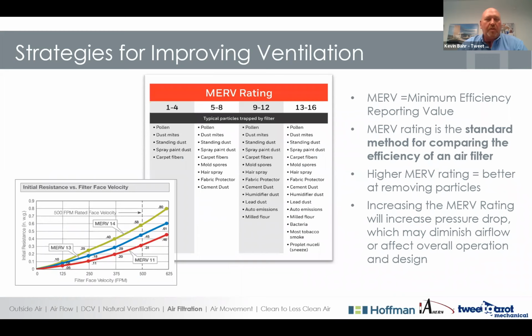Another strategy for improving your ventilation is through air filtration. I'm assuming you all have air filters in your systems, and traditionally they're a lower MERV rating, possibly an 8. MERV stands for minimum efficiency reporting value. It's how their particulate capture capability is measured. As you increase to a higher MERV filter, which seems like an easy resolution, you take your filters out and you put in a MERV 13 or higher, just please be aware.